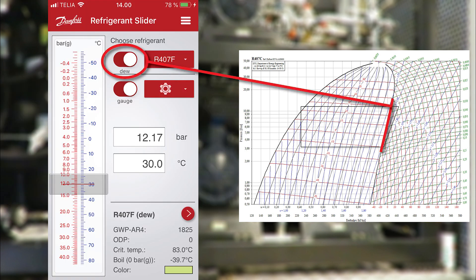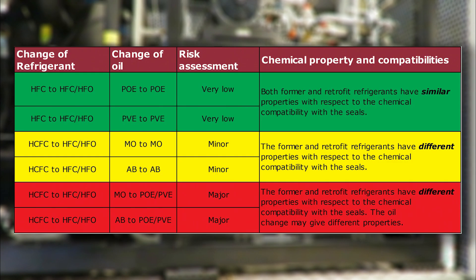Be sure to check and adjust the superheat if you do go ahead with the retrofitting, and remember that it should be the dew point temperature that determines the basis for the new superheat setting. Finally, remember that a retrofit is not something you just do unless you're a professional, so please consult also the refrigerant manufacturers for compatibility, especially when it comes to oil.